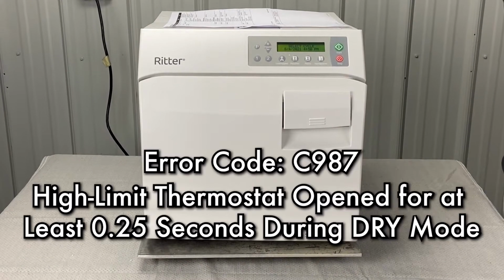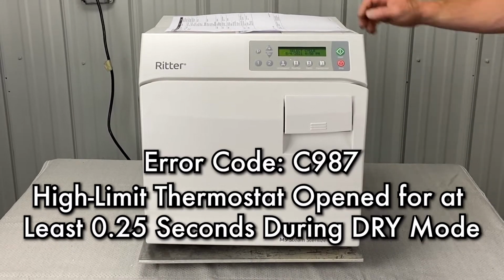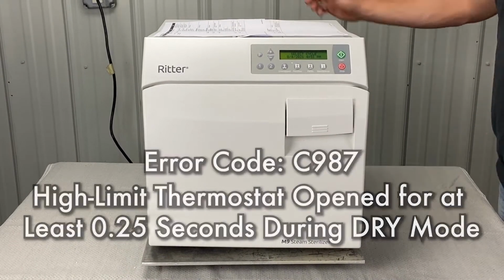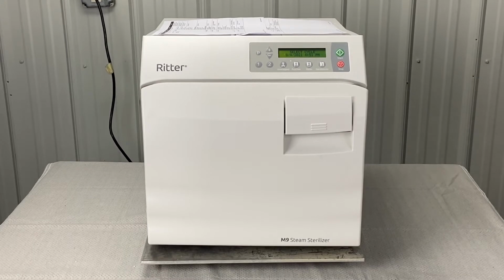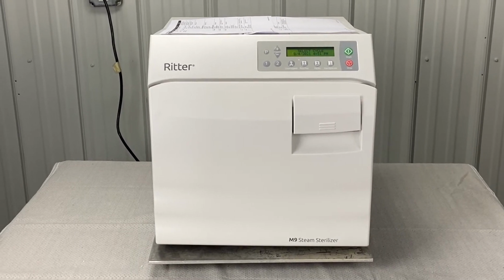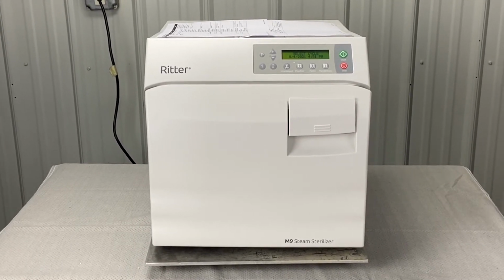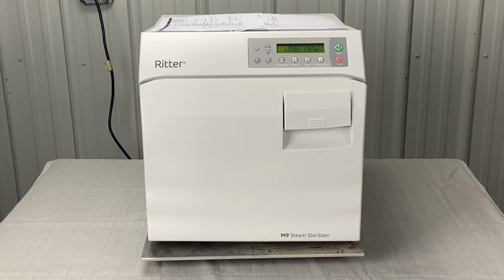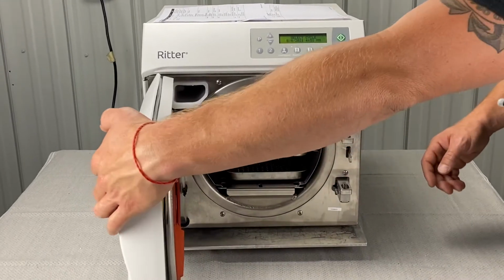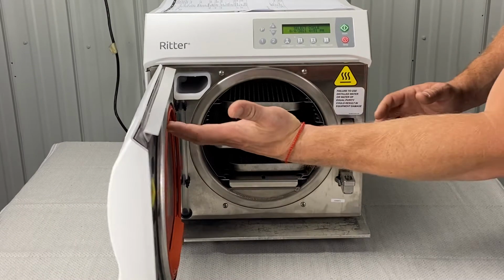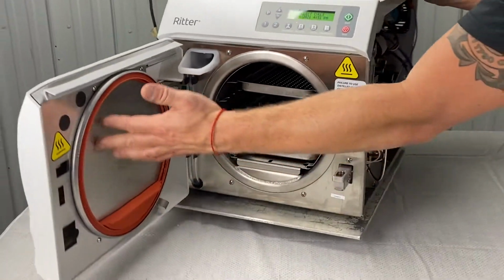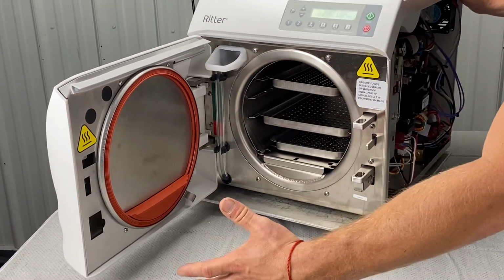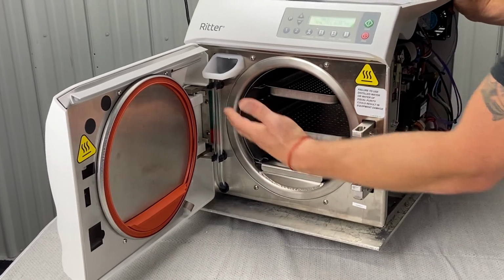Okay, Charlie 987. Charlie 987 error code is the one we're going to talk about. Very common error code. There's any number of issues that can happen. First, what I would like to do is pull all the instruments out and verify your door gasket and your dam gasket are in the correct positioning. Pull all your instruments out. Make sure you've got enough water.